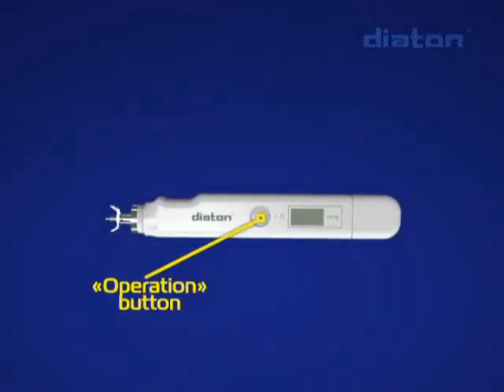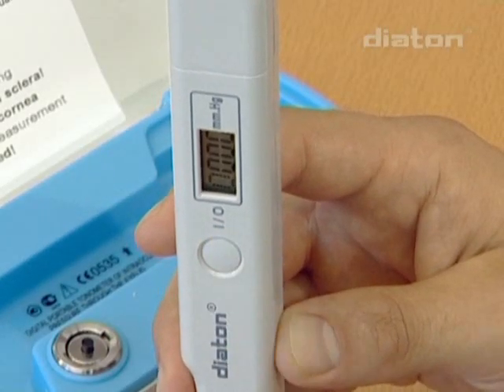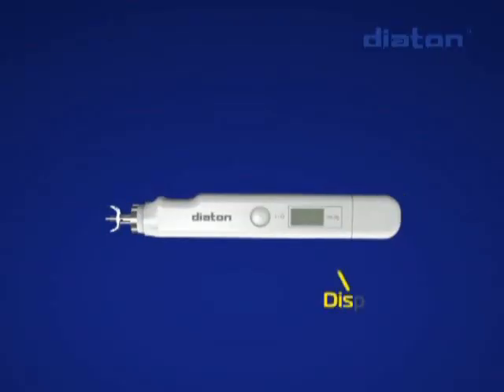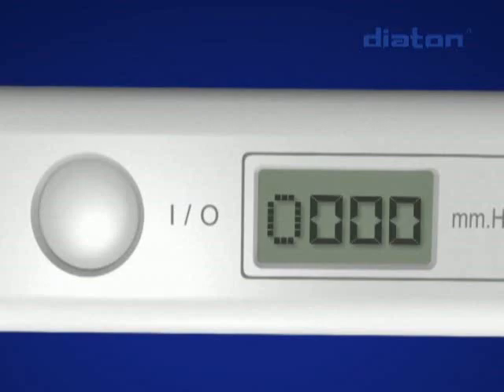The operation button controls the Tonometer's operating modes, including turning on and off, and automated receiving of IOP results through averaging of several measurements. The Tonometry result appears on the display.